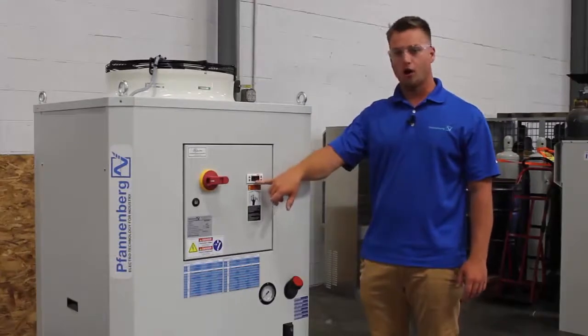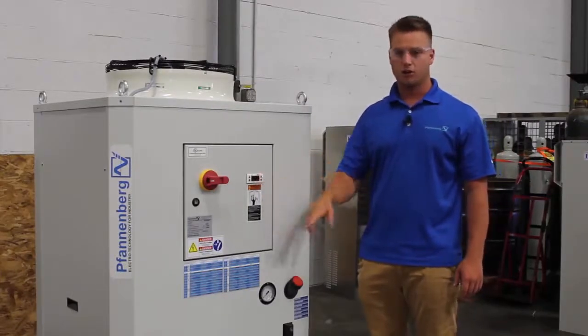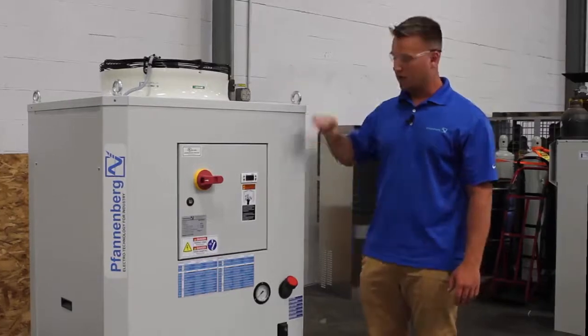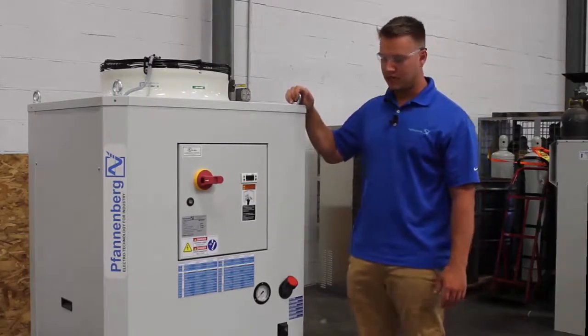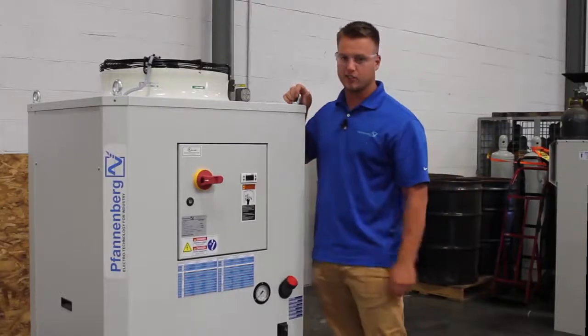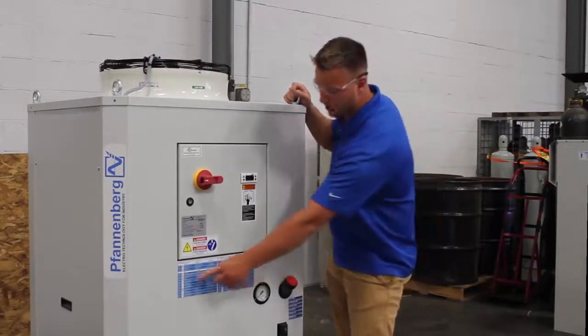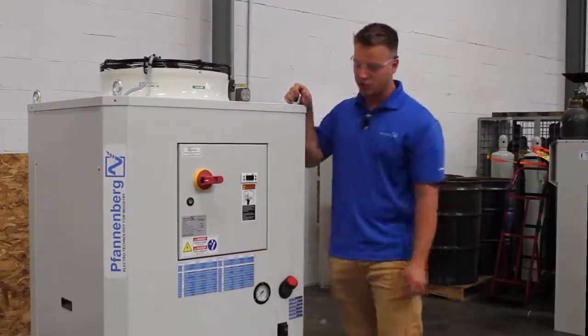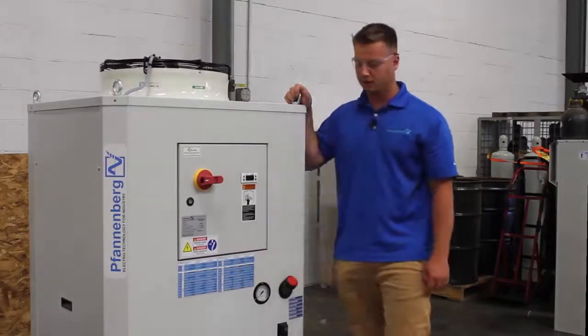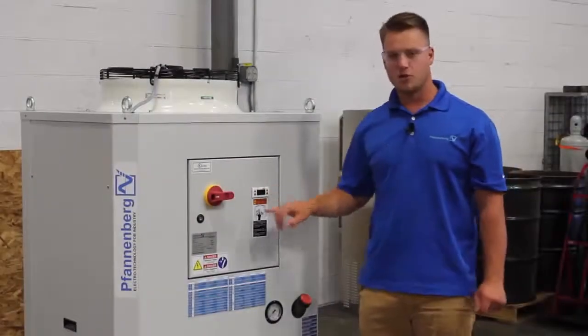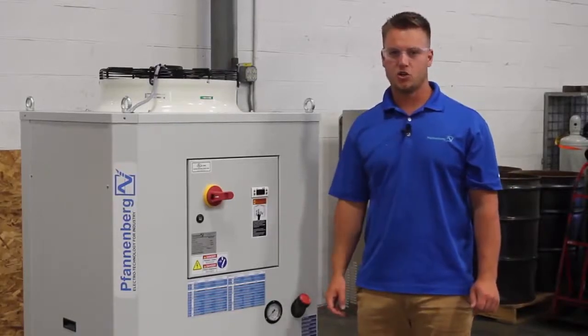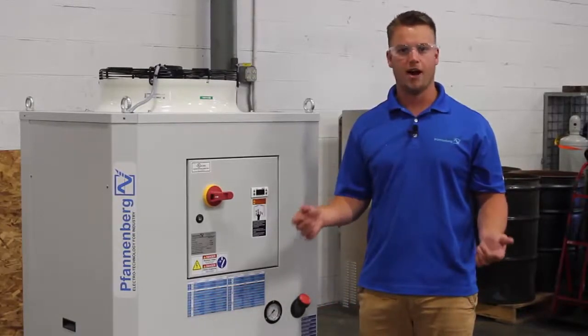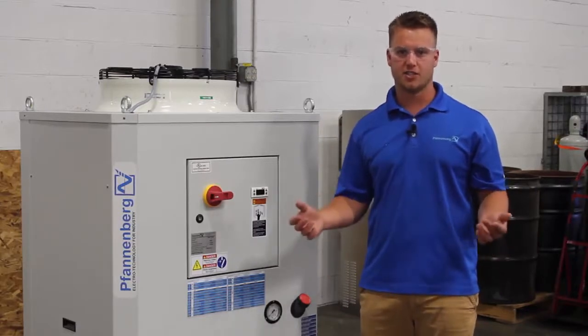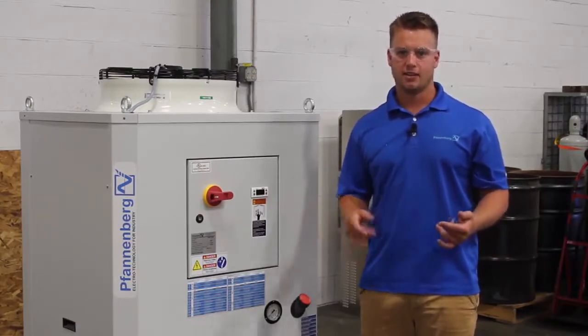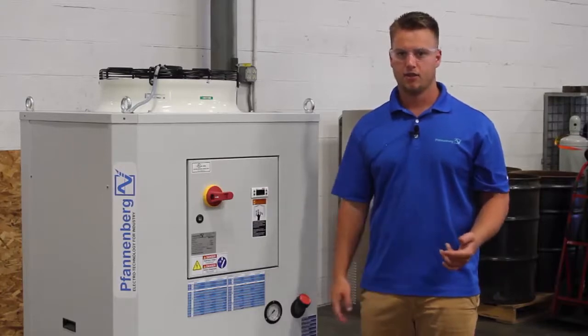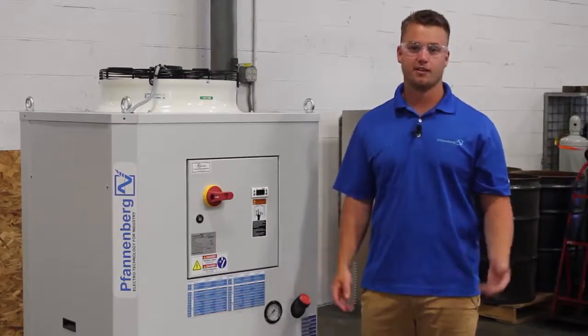This controller will also provide an error code should the chiller go into a fault. For operating purposes, it's very easy to know what the error code that's displayed on the chiller means because we put them right on an error message data label on the front of the chiller. One unique feature about this controller is that it can be controlled via dry contact remote on-off. What this means is that if your system has a remote contact that's on-off, we can turn the chiller on and off from your machine.